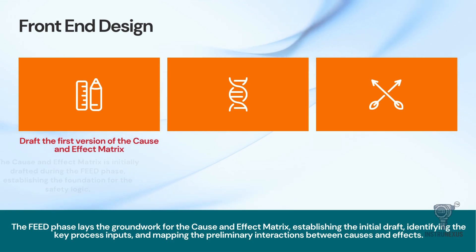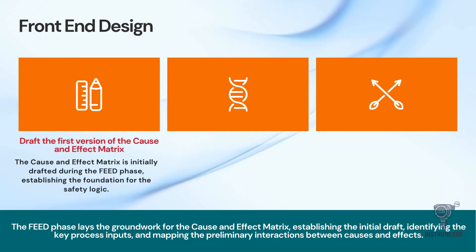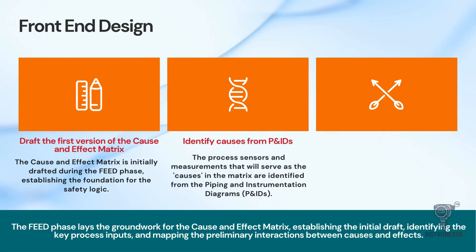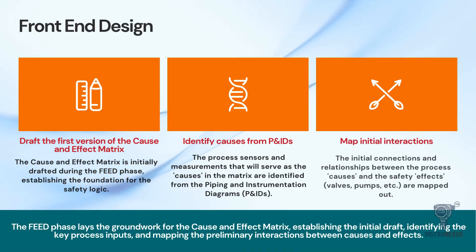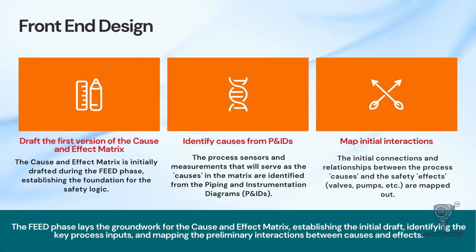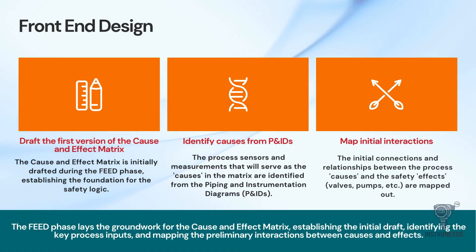Once the concepts are solidified, we move into front-end design, or FEED. This is where the cause and effect matrix is initially drafted. The primary task here is extraction. Engineers look at the piping and instrumentation diagrams, or P&IDs, and identify every sensor and measurement that will serve as a cause. We then map the initial interactions. We aren't looking at the nitty-gritty details of timers or delays yet — we are simply drawing the lines between the inputs and the safety effects, like valves and pumps. This phase lays the groundwork and establishes the foundation for the safety logic that will be developed later.